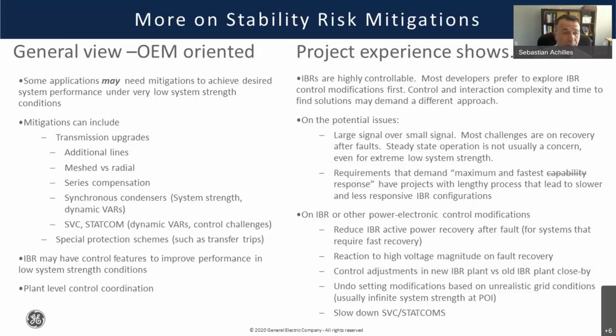SVCs and Statcoms help on one side, and there's additional power electronics that could interact on some others. And then you could have special protection schemes. I know it's something that I try to avoid because it takes a long time to get approvals for those, plus the operation of the grid becomes complicated if you rely too much on special protection schemes to be stable.